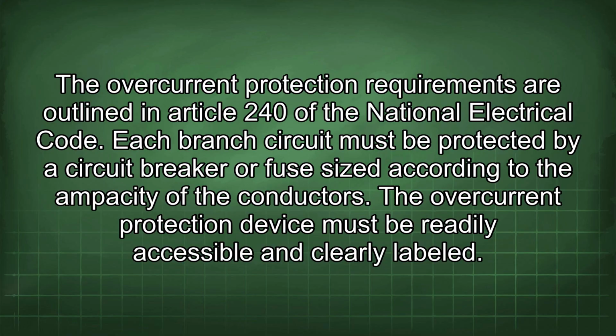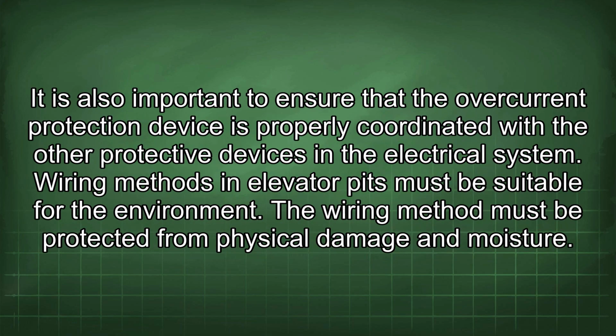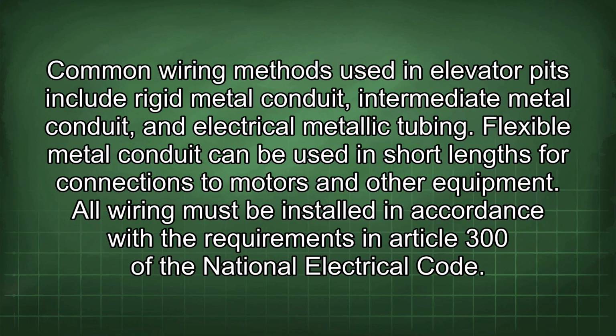Each branch circuit must be protected by a circuit breaker or fuse sized according to the ampacity of the conductors. The overcurrent protection device must be readily accessible and clearly labeled. It is also important to ensure that the overcurrent protection device is properly coordinated with the other protective devices in the electrical system. Wiring methods in elevator pits must be suitable for the environment. The wiring method must be protected from physical damage and moisture. Common wiring methods used in elevator pits include rigid metal conduit, intermediate metal conduit, and electrical metallic tubing. Flexible metal conduit can be used in short lengths for connections to motors and other equipment.